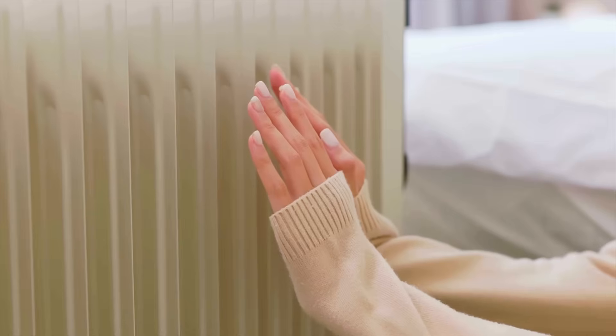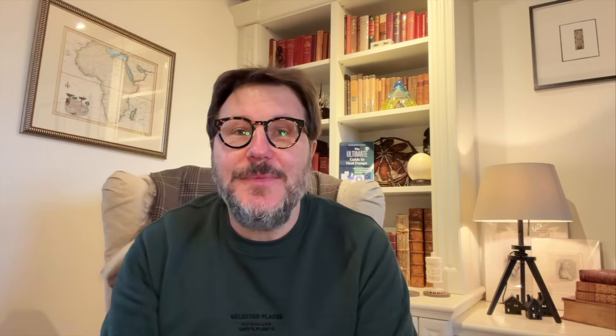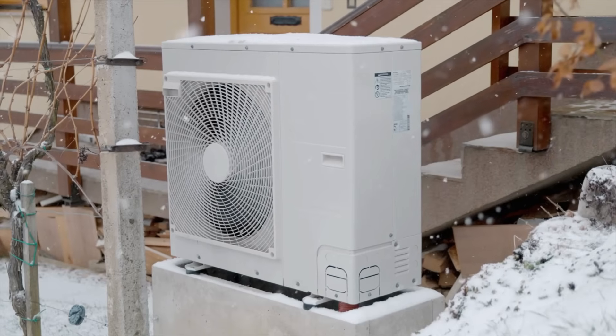Now let's quickly touch on the radiator problem. When weather compensation is working properly, radiators will not always feel hot. On mild days, they may feel barely warm or even cool to the touch — that's normal, that's the system doing exactly what it should. But this is where things often go wrong. Homeowners touch a radiator, feel it's not hot, and assume something is broken. The installer gets a call and, to avoid future callbacks, weather compensation gets turned off or completely overridden. I've even seen installers set fixed flow temperatures at 45 degrees or higher — now radiators feel hot again, but efficiency and comfort disappear. So here's a simple test: if your radiators feel the same temperature whether it's zero or 10 degrees outside, weather compensation isn't working — either it's off or the curve is set way too high. A working system reacts to the weather and you should be able to feel that change over time.